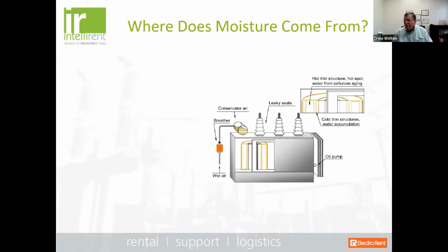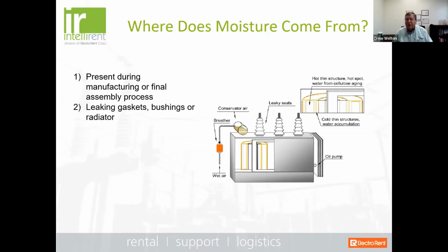Well, moisture can come from a number of different areas, and first and foremost, it can be present during the manufacturing or final assembly process. So it's important when you take delivery of a brand new asset that you know that it has been properly dried out, either in a vapor phase chamber, which is typically done at the manufacturing site before they deliver it to you. And then also you can have an outside influence like leaky gaskets on bushings or radiators, or it can happen during a bushing change out. If you've had a bushing failure or you need to change out bushings, that process can easily allow moisture to ingress into the tank itself. So it's important to do this carefully.